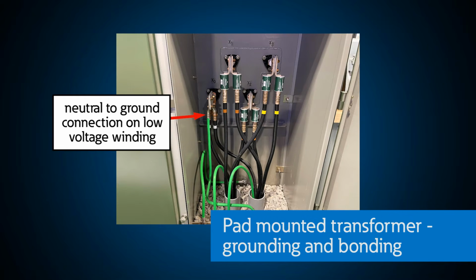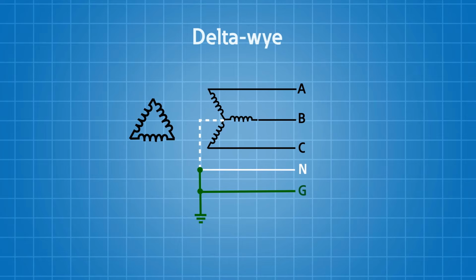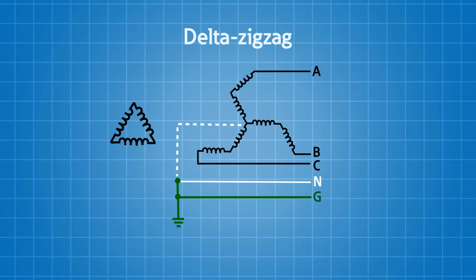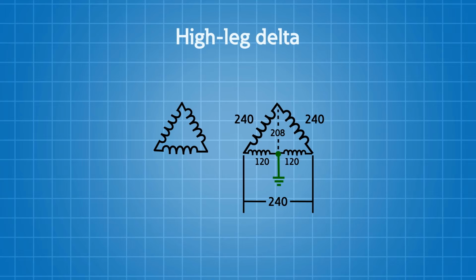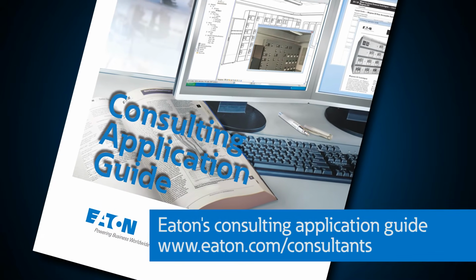Depending upon the winding type, the transformer establishes the configuration that you will have to use. For example, the transformer connection may be a typical one like the delta Y, or maybe more unusual like a delta zigzag or a high leg delta. Well-established methods for grounding and bonding these transformers can be found in our consulting application guide.